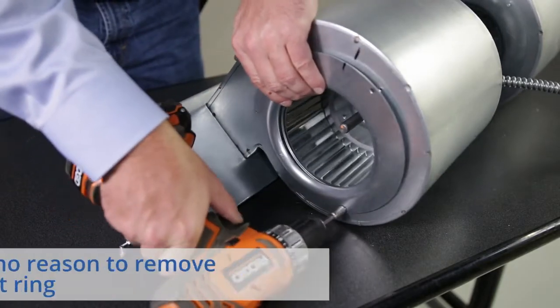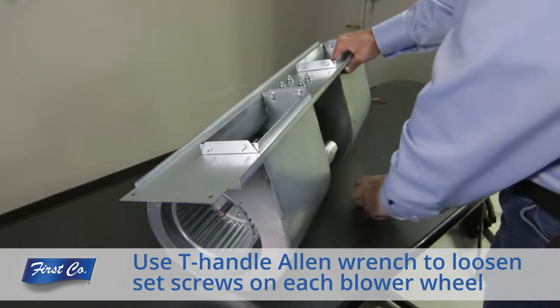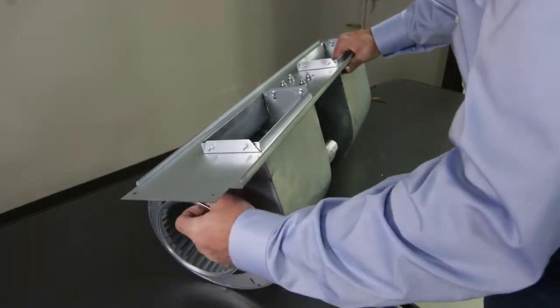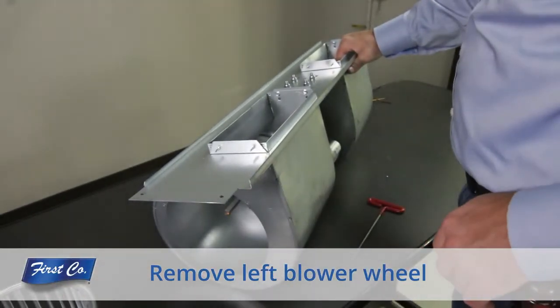Note that there is no need for you to remove the right inlet ring. Turn the blower housing so that you are looking into the blower throat. Using a T-handle Allen wrench, loosen the set screws on each blower wheel. With the set screws loose, remove the left blower wheel out of the side of the blower housing.